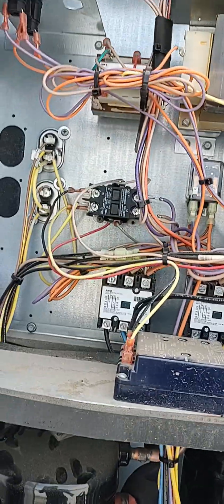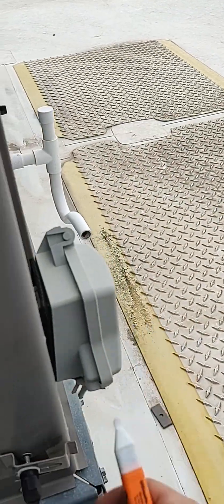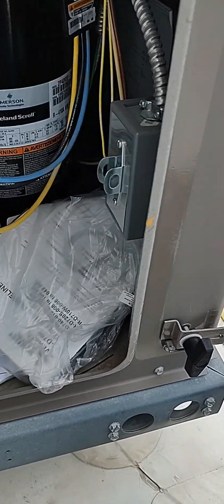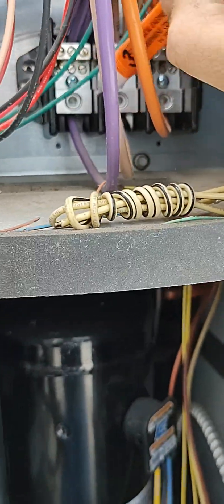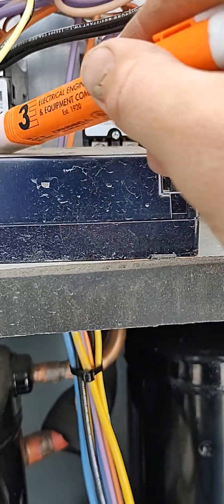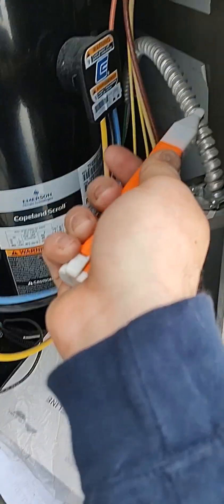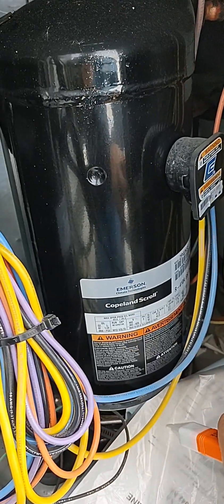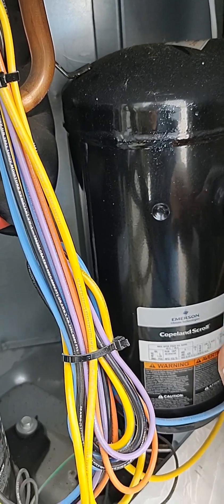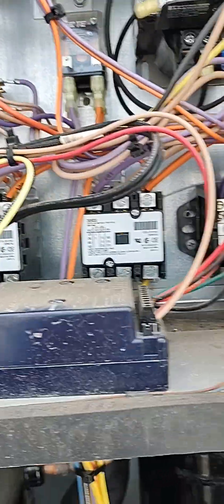The system is completely off. I'll check for power coming in — that looks like 120 volts coming out here. I'll go ahead and shut that off as well and double-check power for safety. We are dead — dead on power. If we're dead here, we're gonna be dead all over.